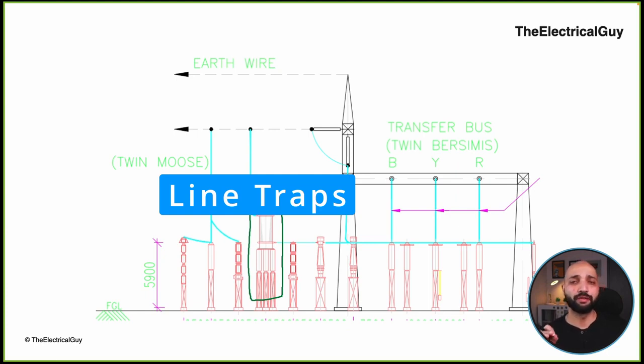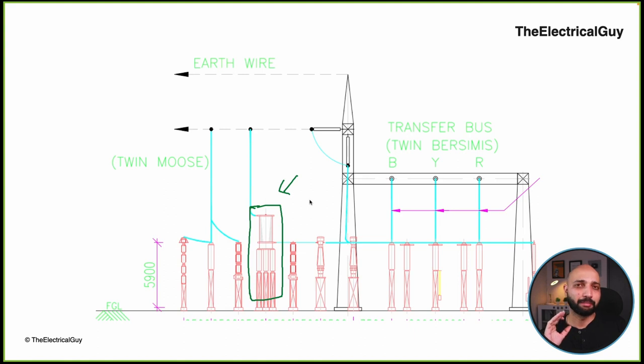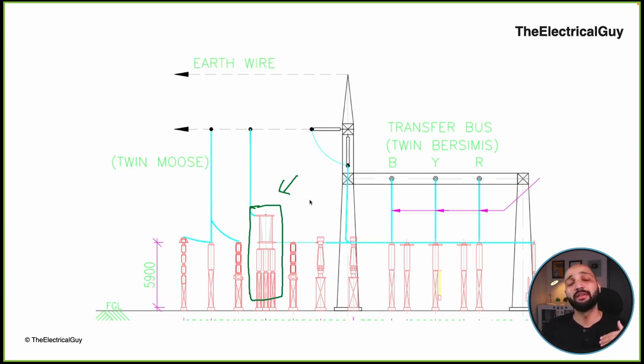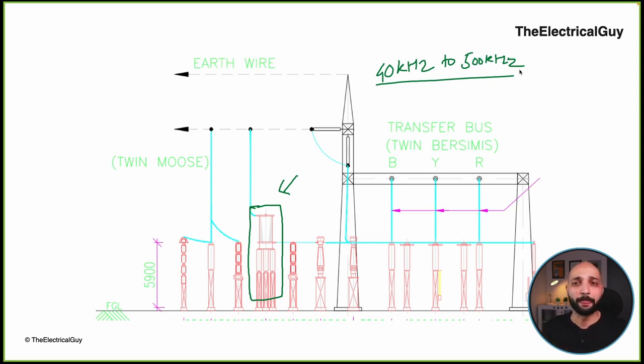Now what is the purpose of this wave trap or line trap? Power transmission lines are not used just to transfer electricity. They are also used to communicate between two substations. So they are also capable of carrying the communication signal, which is at a very high frequency, and that can vary from, let's say, 40 kilohertz to 500 kilohertz. So signals with this frequency also get transmitted via the transmission line. Now if this signal enters the substation, then definitely it will impact the operation of the equipment, especially the transformer. So to avoid this, we use a wave trap.